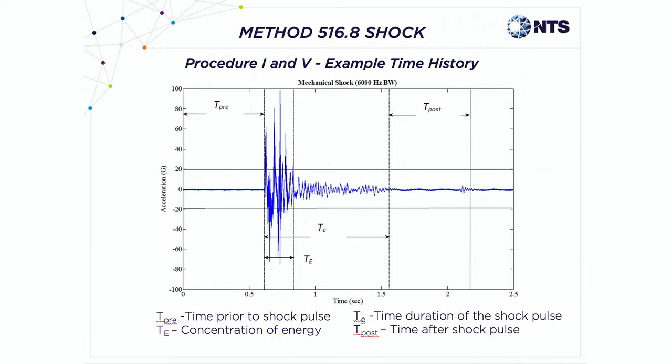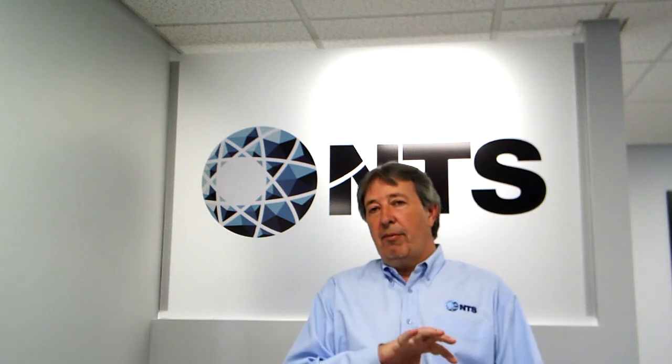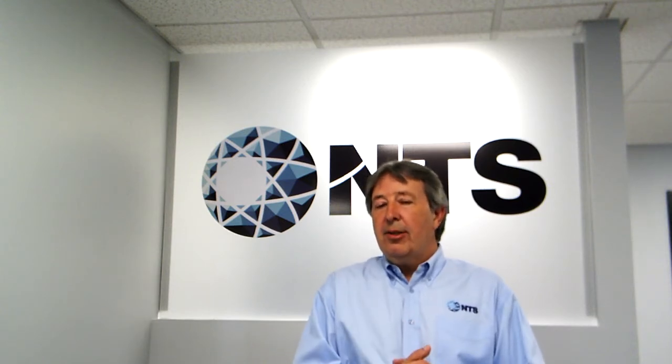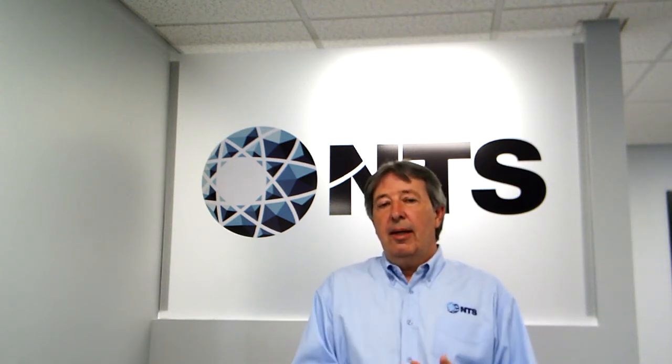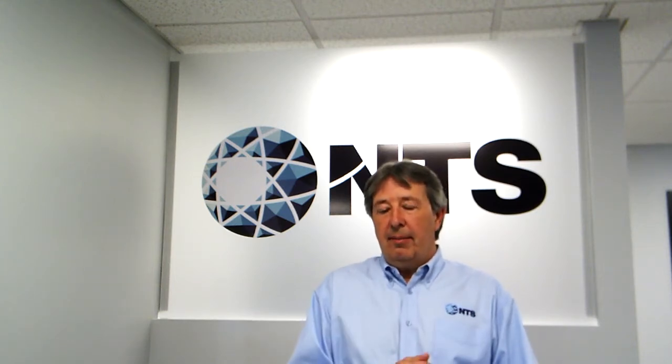If you miss one of those directions, obviously you can spin the unit 180 degrees to catch the other shock axis, as opposed to vibration, which happens in both axes all the time. Or we can reverse the polarity of the pulse. But that's usually not an issue. Usually we can hit both primary positive and primary negative at the same time. Very tight tolerances on them. So that's P1 and P5.